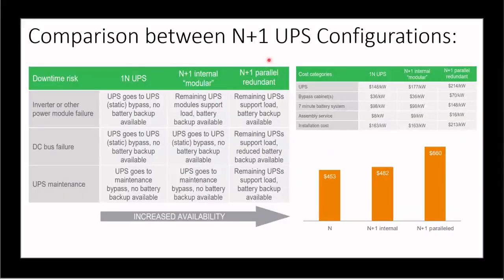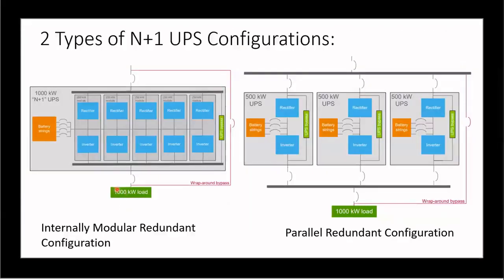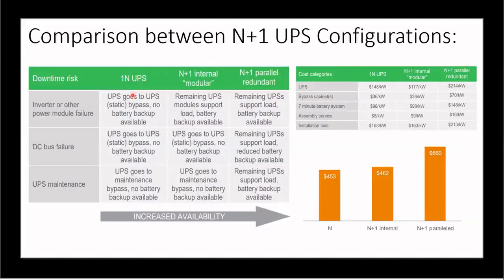So what is N? N is the 1000 kilowatt. Whatever the load is, here we are taking 1000 kilowatt. So N is 1000 plus 1, right? It's called redundancy, so that if something goes wrong, we can always use the extra module or the extra UPS. So this is with no redundancy. There are only 1000 kilowatt power modules, or only UPSs that can support 1000 kilowatt. And these are the other two versions that we sell.